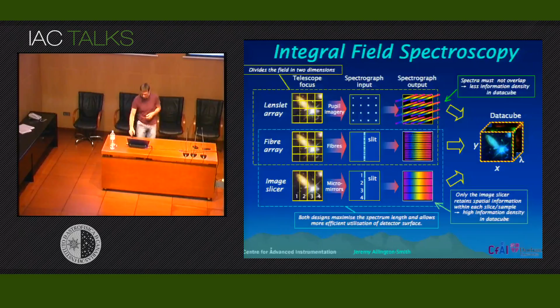So for those of you who don't know integral field spectroscopy very well, I guess there are not many people here that don't know about that. Anyway, there is this slide by Jeremy Allington-Smith that's shown in many IFU related talks. You can see several techniques: lens arrays, fiber arrays, where you always somehow reconfigure the focal plane of the instrument into some kind of slits or slit-like formation, and then you disperse it through the spectrograph. For MUSE, the image slicer was chosen, probably because, as it says here on the slide in the lower right, this gives you the highest information density on the CCD and also in the output data cube.